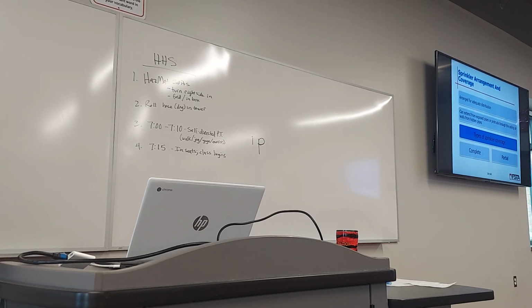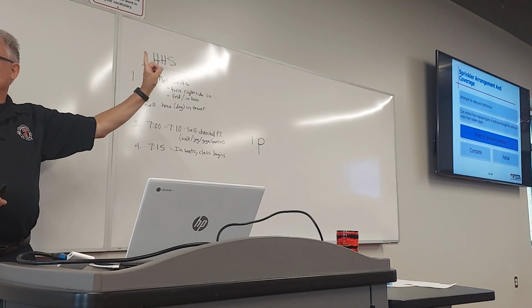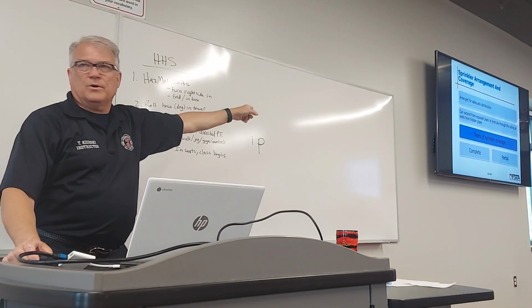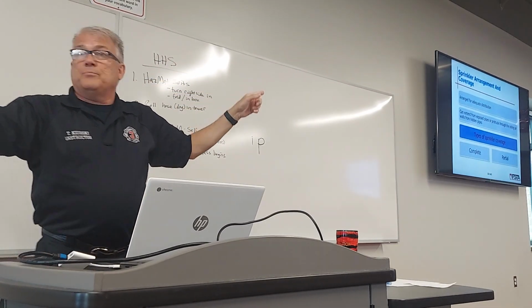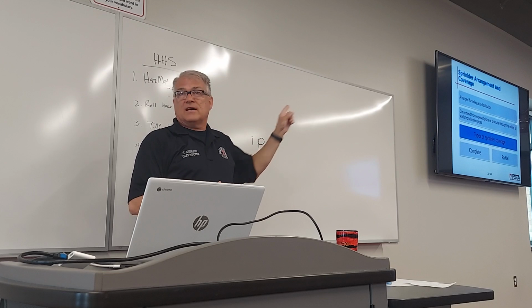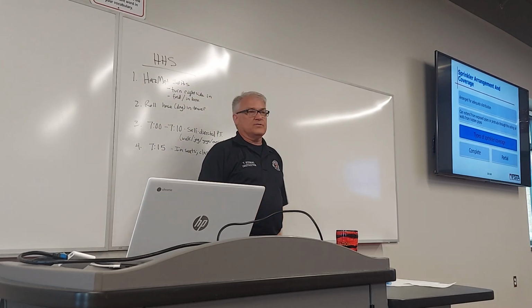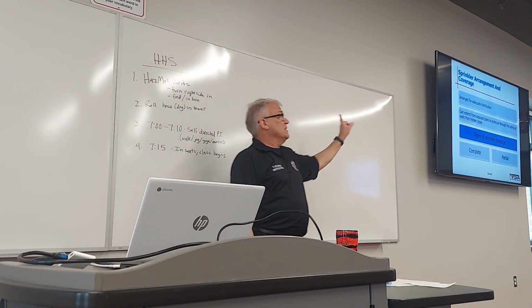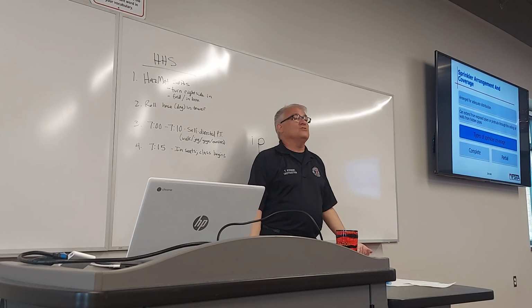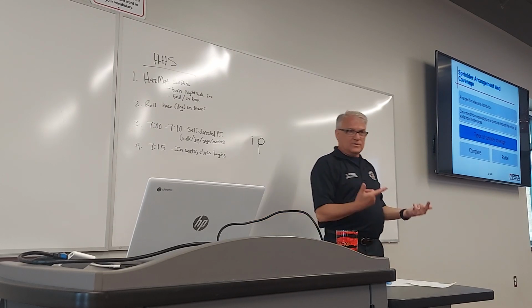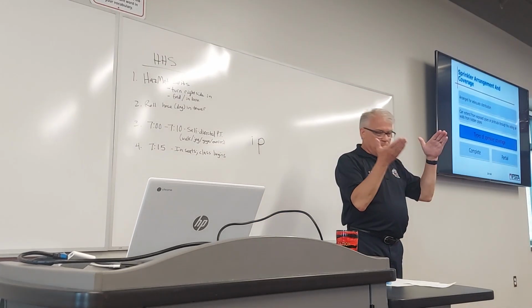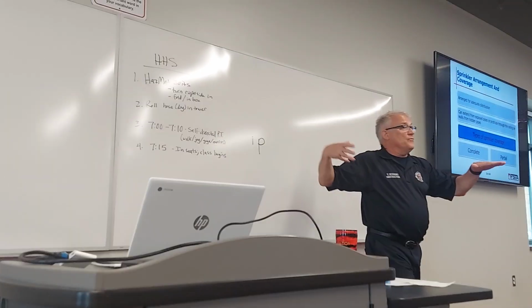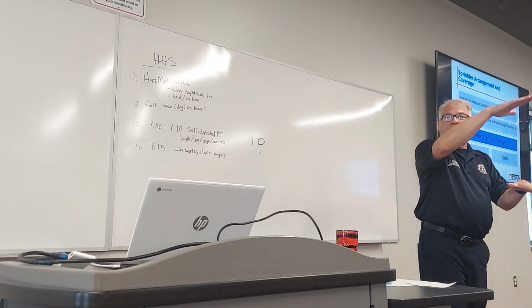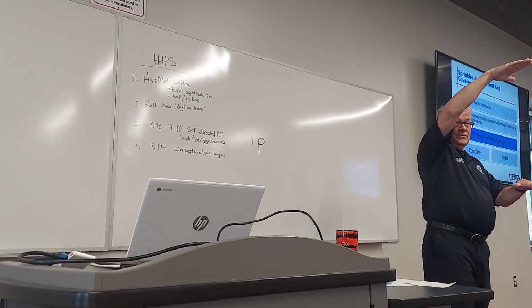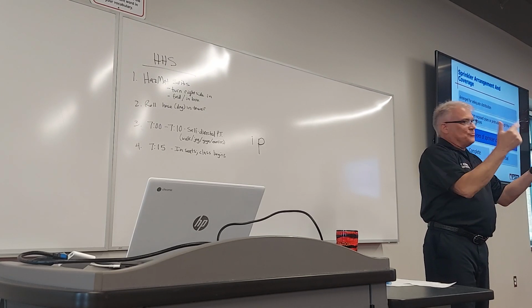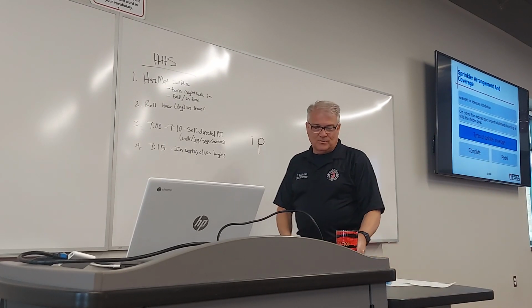Sometimes when people look at buying a building, they see a closed one and decide to put their business in there. The realtor says, 'Look, it's got a sprinkler system—that's a selling point.' But the realtor has no idea that system was designed for a moderate hazard, and you're moving in with a high or extra hazard. It's not correct—you have to refit the system for it to work.